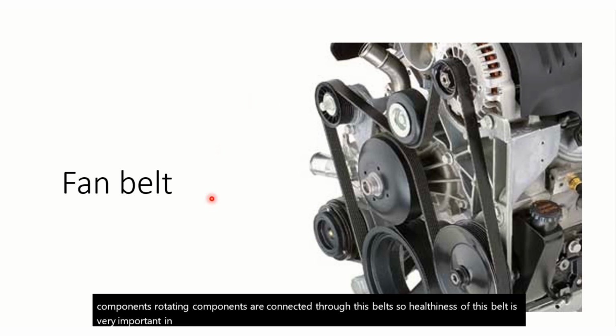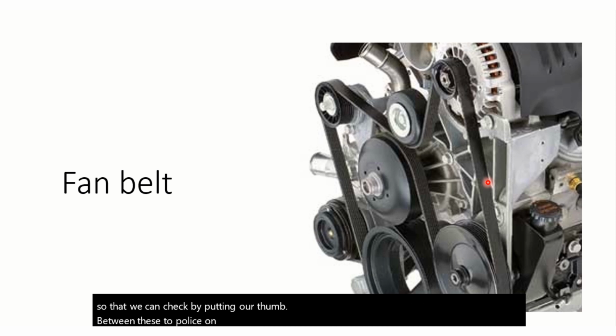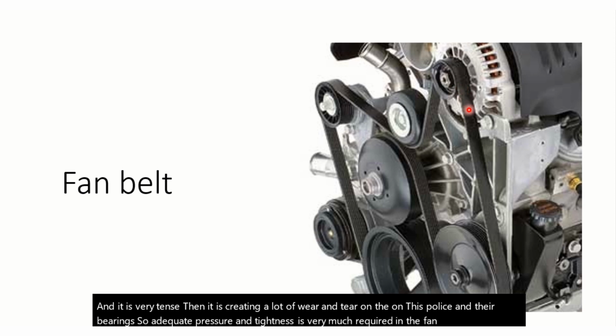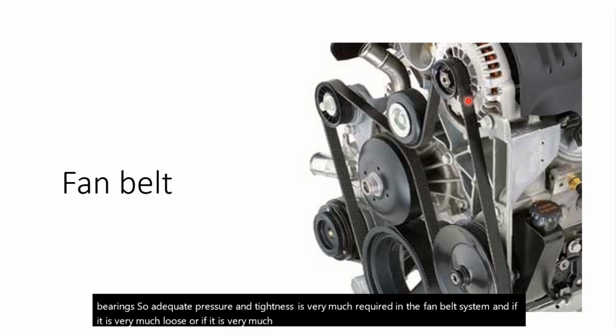In the fan belt checks, we have to ensure the correct tension of the fan belt. We can check by putting our thumb on the belt between two pulleys, and we have to ensure that the belt can be pressed down up to half an inch without putting any extra pressure. If it goes down half an inch easily, then the tension is correct. But if it is very hard and very tense, it creates a lot of wear and tear on the pulleys and their bearings. So adequate tightness is very much required in the fan belt system, and if it is too loose or too tight, we have to readjust it.